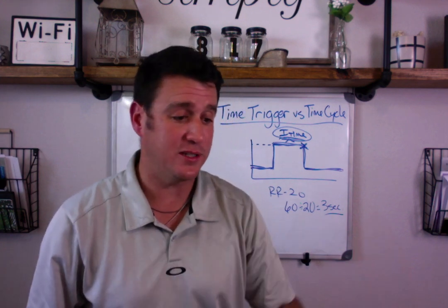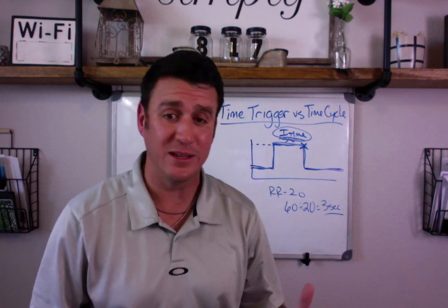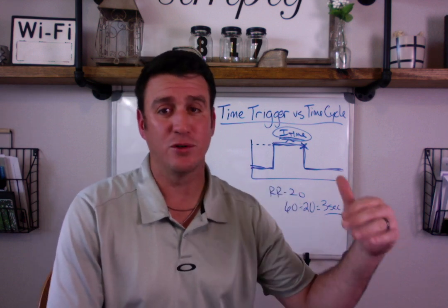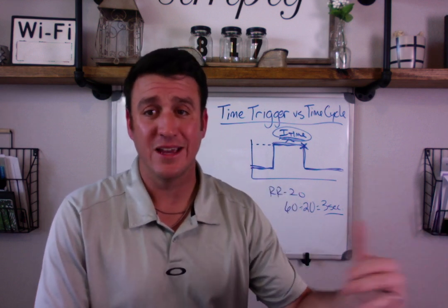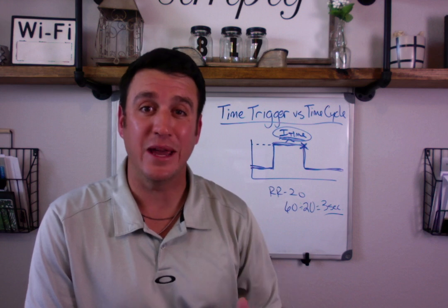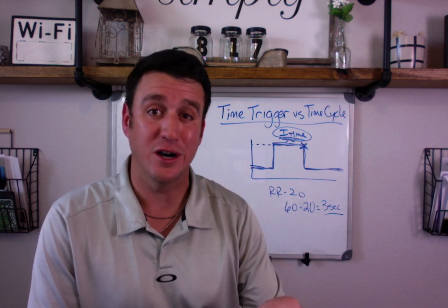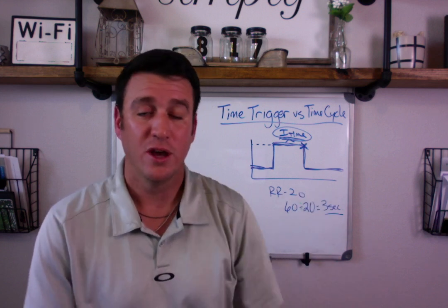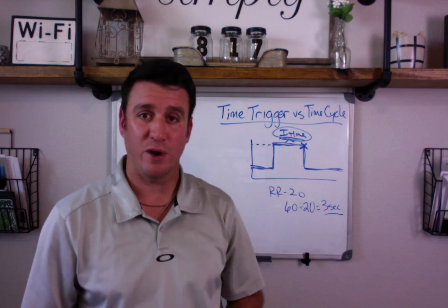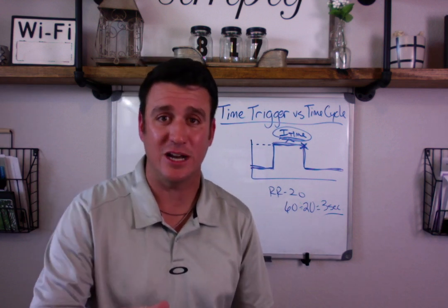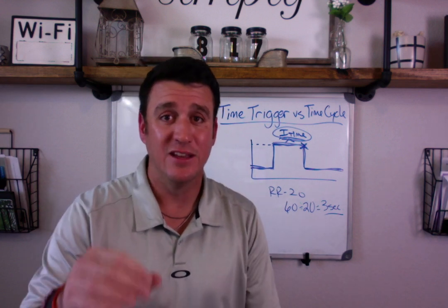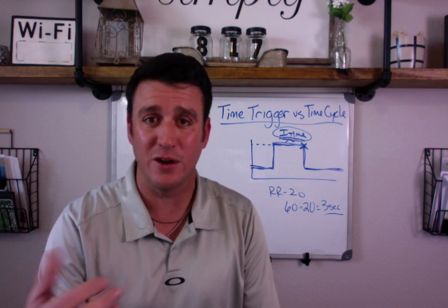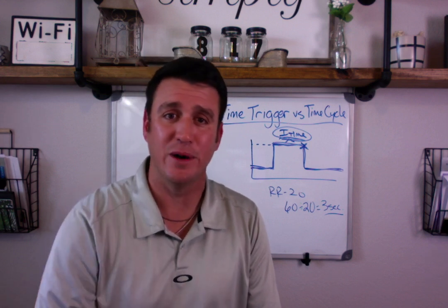So the answer to your question, Eugio, is simply this: time triggered is based off of total cycle time. Time cycle is based off of I-time, which is set by you, the respiratory care practitioner. I hope this makes sense. Leave me lots of comments, any questions, any concerns — if it doesn't make sense, please follow up.